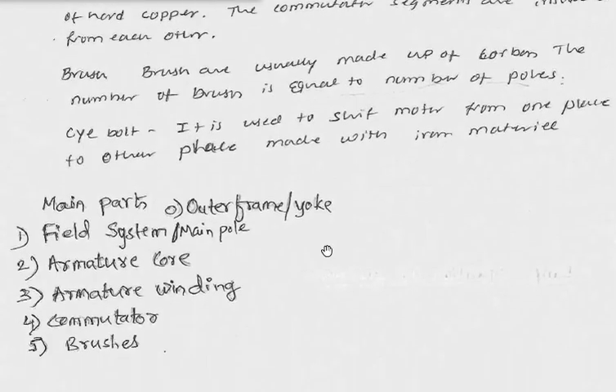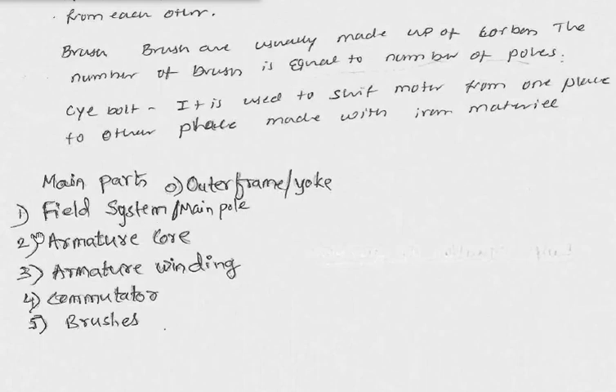The main parts are: outer frame/yoke, field system or main pole, armature core with armature winding, commutator, and brush. The commutator is made of hard copper and commutator segments are insulated by mica. The brush is made of carbon and rests on the commutator segment using a spring arrangement to maintain firm contact.